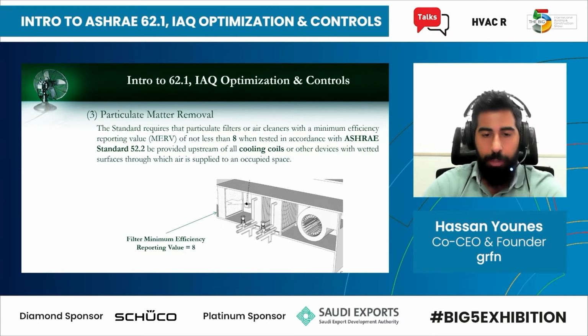MERV 8 is the requirement in the 2016 version. Before that, it was MERV 6. That will introduce a little bit of higher pressure drop on your fan, so you might need to increase the fan capacity in terms of static pressure. That might increase the cost or the running cost of that fan, but it's important to have this high efficiency filter to capture contaminants.